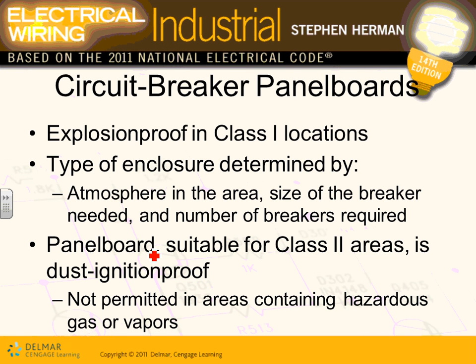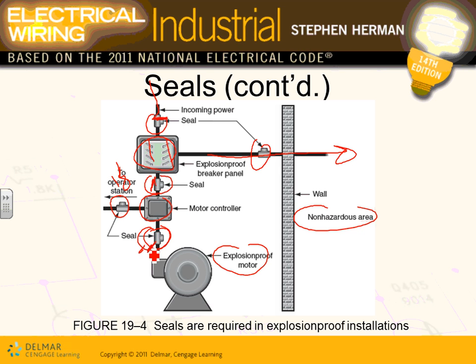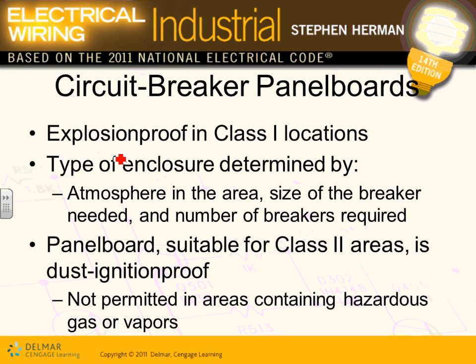Okay, circuit breakers. Can you guys see this panel? They have an explosion-proof panel, right? This is exactly like this one, except it's 10 times more expensive. Could it handle an explosion? Circuit breaker panels, explosion-proof in Class 1. If you put them in a Class 1 Div 1, it has to be explosion-proof. The type of enclosure is determined by the atmosphere, the area that you're in, the size of the breakers, and the number of breakers that you need, like any other panel.